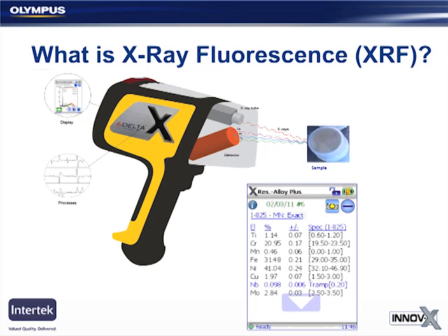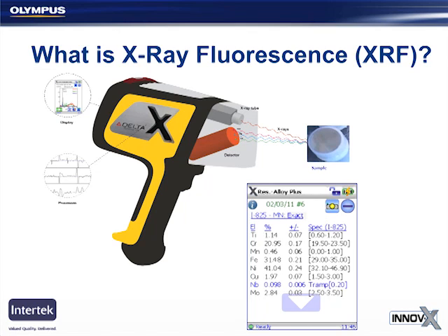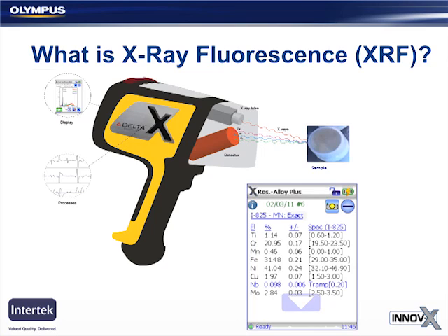The X-rays that return from the different elements in the sample and go back to the analyzer have different energies or wavelengths, which you can think about as having different colors. It's not exactly the same thing, but the analogy sort of holds. A detector in the analyzer collects all of these X-rays, and software on the analyzer can translate that information into what elements are present and how much of those elements are present. The user sees a readout on the screen on the analyzer or on an attached computer on what elements are present and the concentrations. The readout might look something like this.